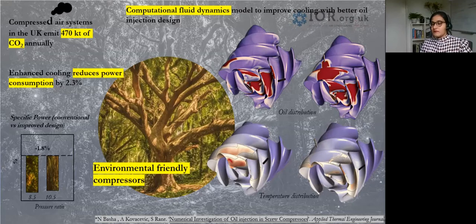Therefore, if you take the same amount of oil, shown on the right-hand side of the figure, and distribute it evenly, the oil is well distributed and that reduces the temperature spots in the compression chamber. The difference between the conventional and improved design is a reduction of 35 to 40 degrees in compression chamber temperature, and this reduces power consumption by 2.3%. More importantly, the specific power is reduced by 1.8%.